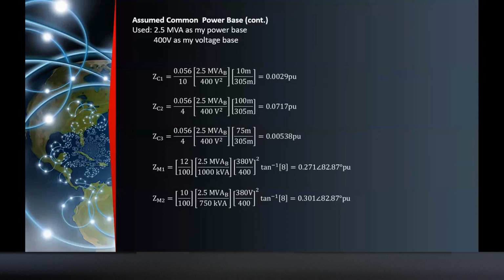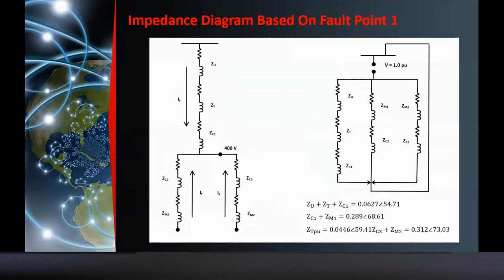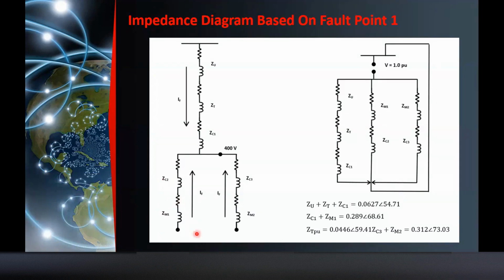Okay? After you have converted everything to per unit, what is the next thing to do? Class, you can read that in the procedure. I went straight to the diagram. Once you have converted to per unit, on the left side of the diagram is your impedance diagram based on fault point 1. Earlier we converted to per unit the utility, the transformer, and the cable. And you have motor 1, then the cable. Motor 2, then the cable.